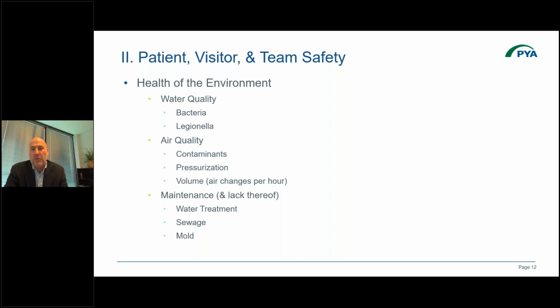Air quality, contaminants. One of the big factors during construction is dust. We talk about cross-contamination. We talk about pressurization. For instance, we talk about occupied spaces within hospitals, renovation projects that are either on the same floor or within an adjacent space above or below active patient care areas. We want to keep all those contaminants, all that dust, all of those issues within that construction space and not send them out into the clinical spaces. At times, we've seen where this happens. There are documented situations where poor quality control, not enough oversight, bad planning and communication can cause contamination within patient care areas.